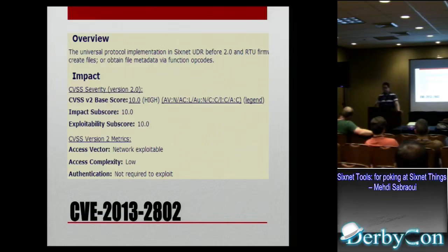Sixnet's response was that we weren't using the latest version firmware. We pulled the firmware right off their site right before we started doing anything, so to us it was the latest. Apparently there's a new firmware that hasn't been released widely that completely solves all of this nonsense. It had been created for a specific client. It's due to release before the end of the year. It adds everything that this is missing, which is the authentication and authorization.